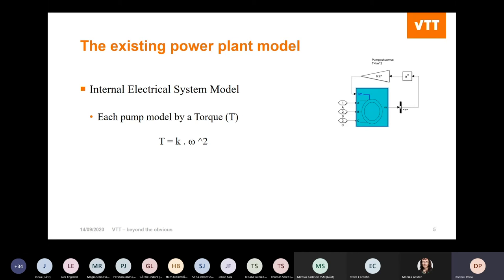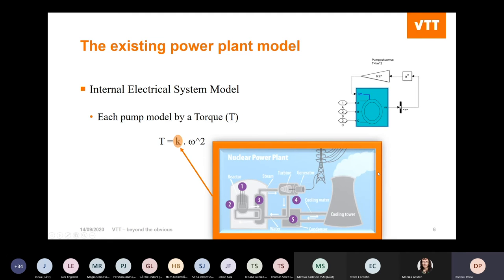When we want to simulate the electrical system — for example the internal system — we place a motor, like a symbol in MATLAB Simulink, and create a feedback with a simple equation where torque is proportional to speed squared. This is how the thermomechanical system is reduced to one simple coefficient. That's how the electrical system inside the power plant has normally been simulated until now.